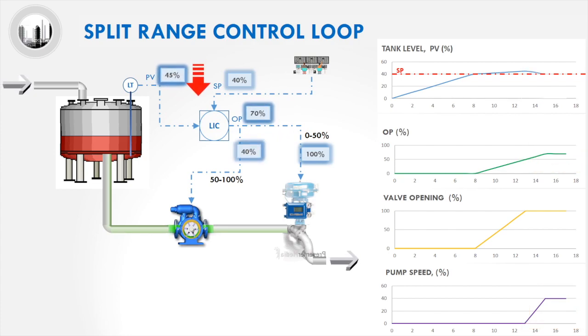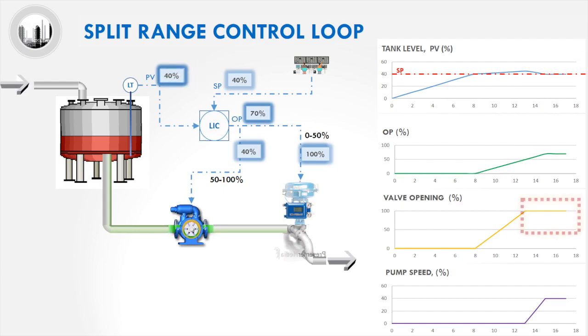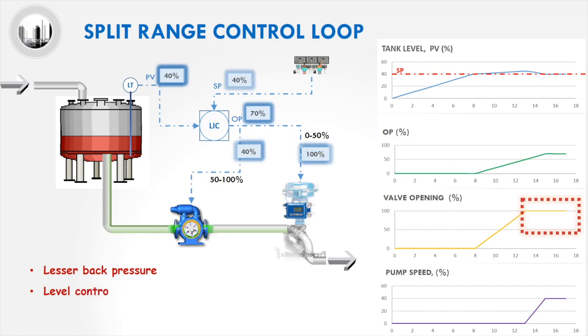In this example, we observe that the control valve opening is always at 100%. With the control valve fully open, there is less back pressure to the pump. The control valve will also be subjected to lesser wear and tear as it always stays at 100% and is not throttling.